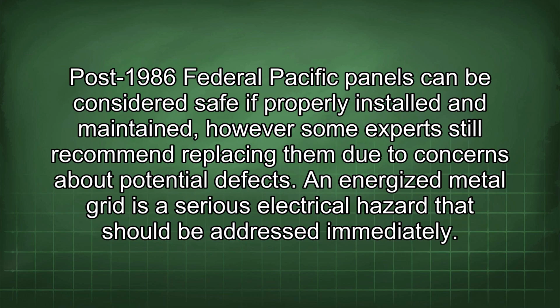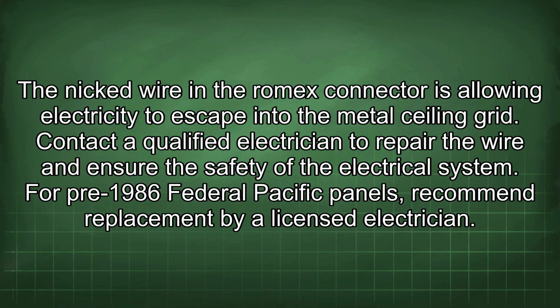Post-1986 Federal Pacific panels can be considered safe if properly installed and maintained. However, some experts still recommend replacing them due to concerns about potential defects. An energized metal grid is a serious electrical hazard that should be addressed immediately. The nicked wire in the Romex connector is allowing electricity to escape into the metal ceiling grid. Contact a qualified electrician to repair the wire and ensure the safety of the electrical system.